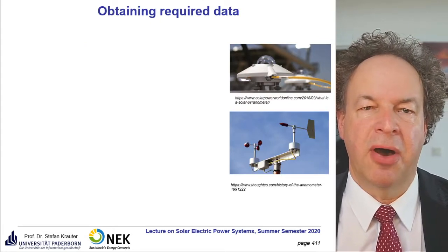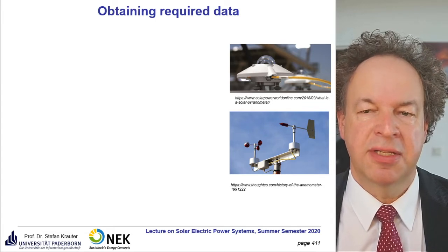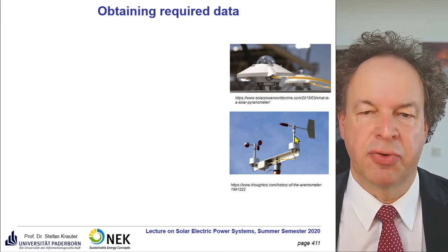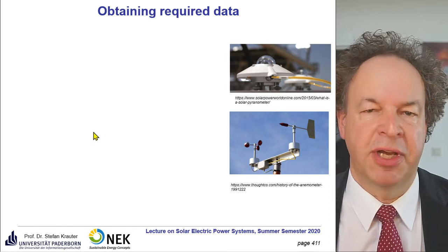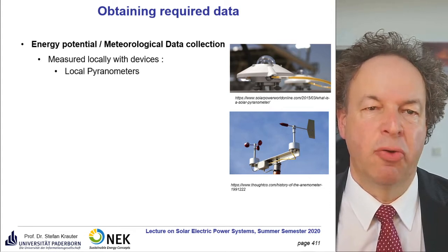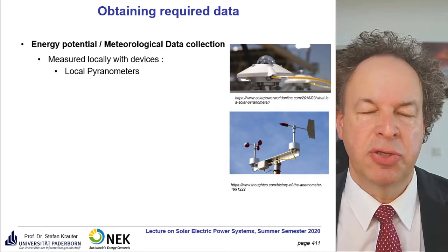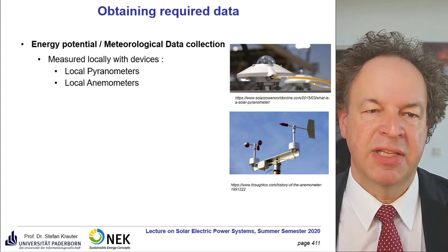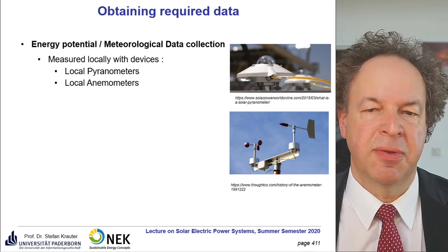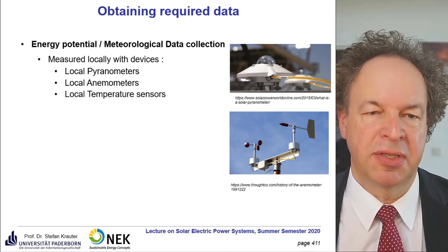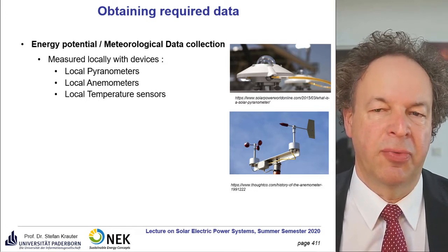For obtaining required data, remember the chapter where we discussed irradiance. We have here a pyranometer — we measure it ourselves. If you have a second source such as wind, you should also measure the wind potential. Best is local pyranometers on-site, but you should measure for a long time — at least one year. The same applies for local anemometers. For wind, because potential changes, you should measure longer than one year, preferably around 10 years. Temperature sensors are also important because temperature influences system performance, as you know from the performance ratio.